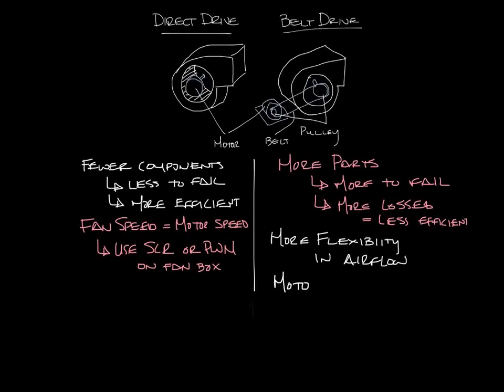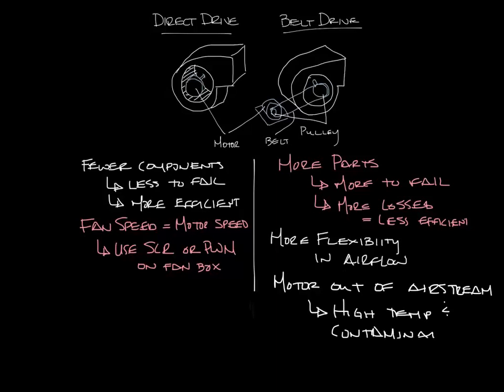In a belt drive fan, the motor is outside of the air stream. So this is good if you have applications where you don't want the motor in the air stream, like high temperature applications or contaminated air applications. Also, larger fans typically run at lower speeds which you can achieve with the pulleys. Whereas lower RPM motors might be more expensive or the motor just can't be turned down that far.